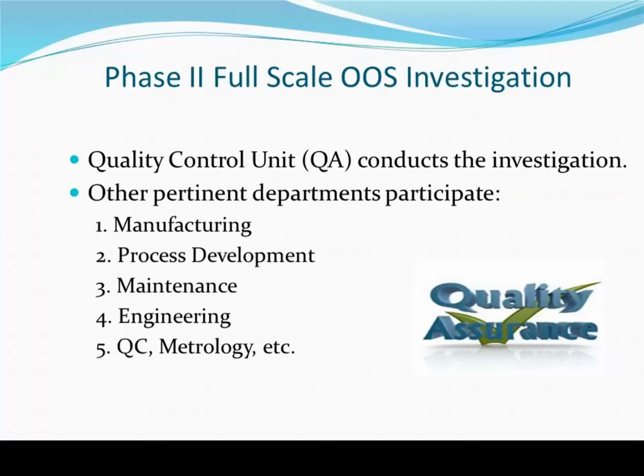And QA will oversee the investigation. They don't usually conduct it, but they will oversee it. You can certainly get a group together to help look at the actual issue. I always like to get some people who aren't really familiar with the test or the process involved. They put a new set of eyes on things. So, maybe have a nice cross-functional group, maybe pull in a maintenance individual, maybe engineering, validation, really up to you, but a nice core group of individuals that can look at things a little bit more objectively.